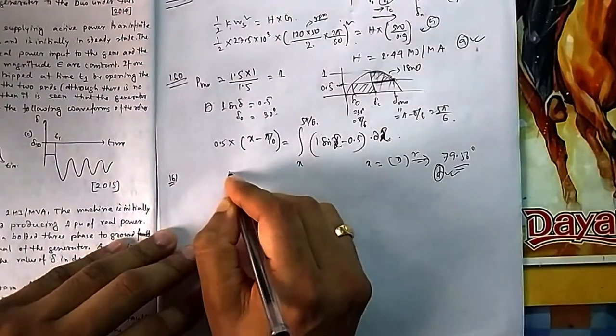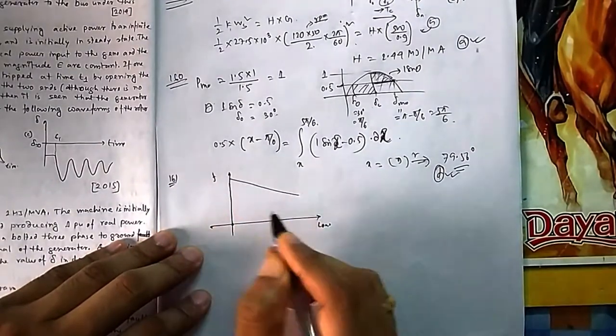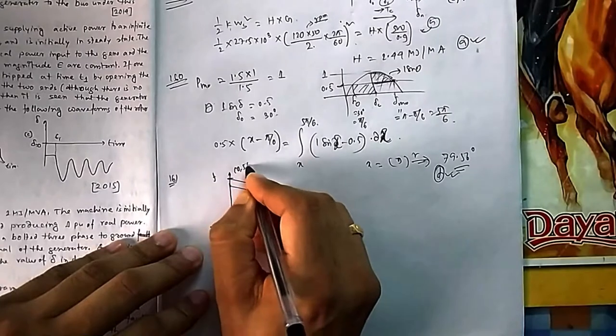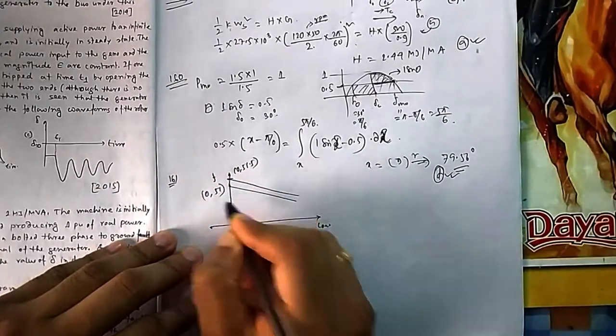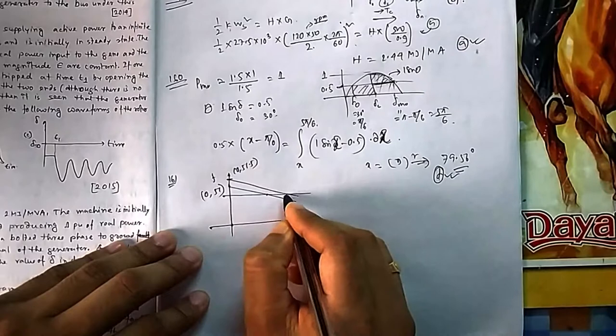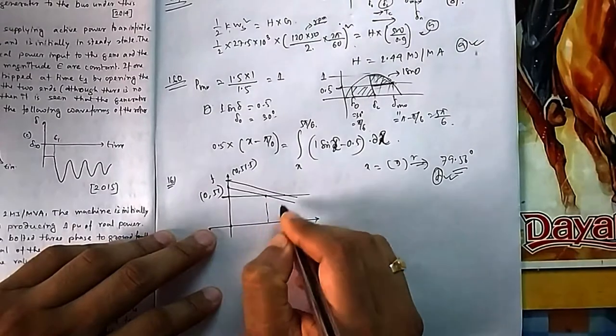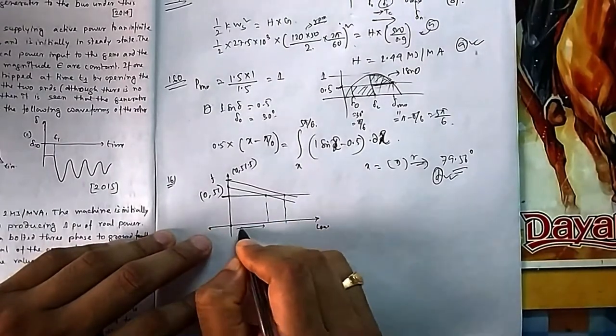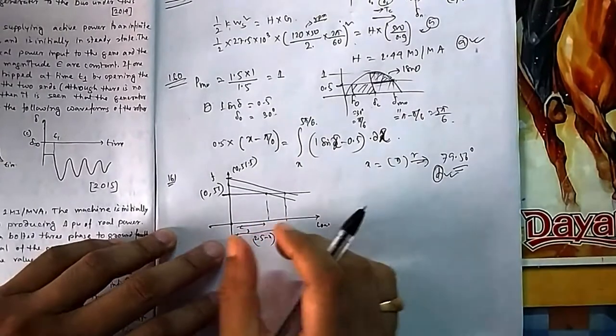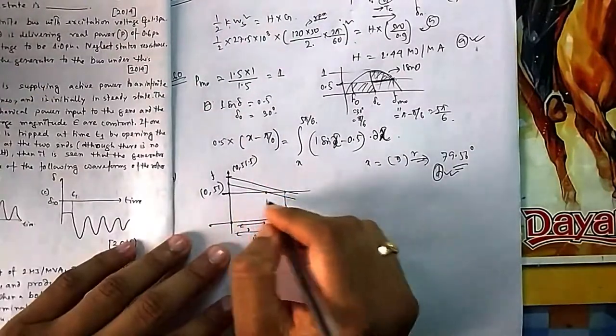On the load-frequency plot, at zero load the first generator has frequency 51.5 Hz and the slope is minus 1 Hz per megawatt. Since both slopes are equal, the lines are parallel. They operate in parallel at the same steady-state frequency. If generator 1 supplies x, then generator 2 supplies 2.5 minus x, because the total load must equal 2.5 megawatt.